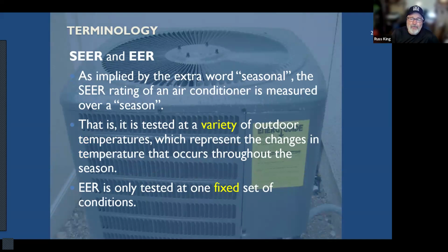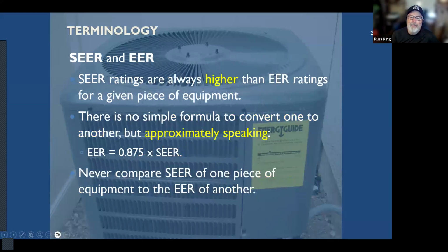As implied by the extra word seasonal, it just means it's measured over a season, so it's subjected to varying conditions. And then the EER is tested at fixed conditions. For some strange reason, SEER ratings are always higher than EER ratings for a given piece of equipment. There's no real direct correlation between the two. Some pieces of equipment will test very well at the SEER rating and then not so well at the EER rating, and vice versa. But roughly speaking, the EER is the SEER times 0.875. Don't assume that's the case, though. It's just an approximation. Never compare the SEER rating of one piece of equipment to the EER rating of a different piece of equipment. That's apples and oranges.